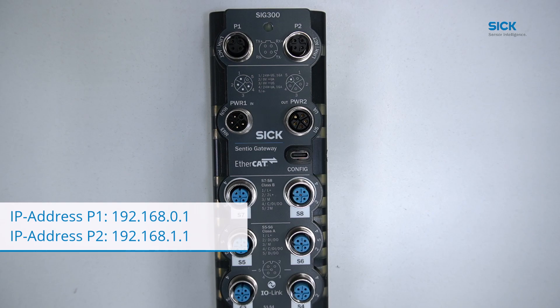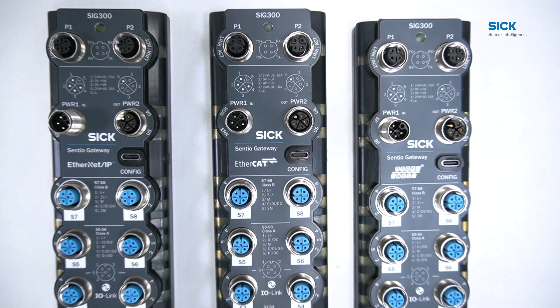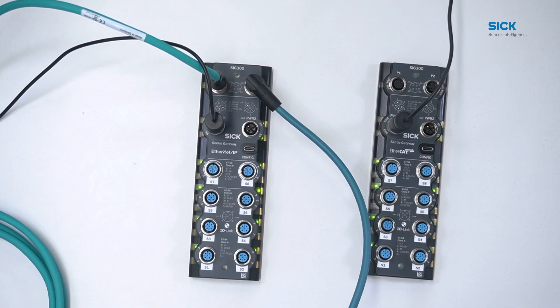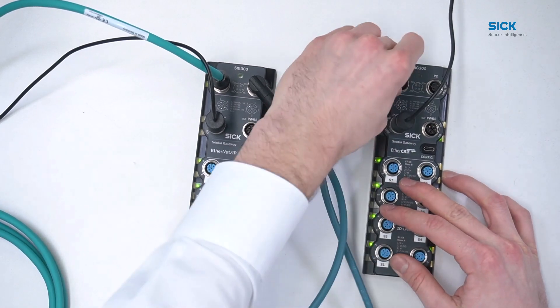For the EtherCAT, Ethernet/IP, and PROFINET versions of the SIG300, the Ethernet ports are bridged, making the device a dual-port network switch. Therefore, the SIG300 can be connected to a PLC system via Ethernet cable through either one of the two Ethernet ports. By being a dual-port device, it furthermore enables the connection of multiple devices in series, better known as daisy chaining. The Ethernet connection comes in through one Ethernet port and out through the other to the next device.